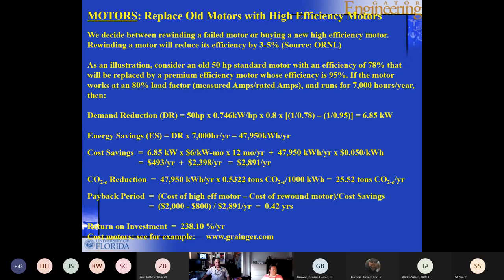So as an illustration, we're going to take a 50 horsepower standard motor, let us say, with an efficiency of 78%, and that will be replaced by a premium efficiency or a high efficiency motor. In this case, I'm just going to use the two words interchangeably. It has 95% efficiency. Now, assuming that the motor is going to work at an 80% load factor, by the way, the load factor is defined as the ratio between the measured amps. You can get an amp meter and measure the amperage across the motor windings and divide that by the rated amps on the nameplate for the motor, and you will get a ratio, or a percentage, depending on whether you multiply it by 100, 0.8 or 80%.